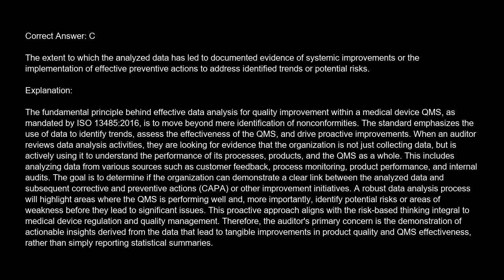The correct answer is C. The extent to which the analyzed data has led to documented evidence of systemic improvements or the implementation of effective preventive actions to address identified trends or potential risks. Explanation: the fundamental principle behind effective data analysis for quality improvement within a medical device QMS, as mandated by ISO 13485:2016, is to move beyond mere identification of nonconformities.